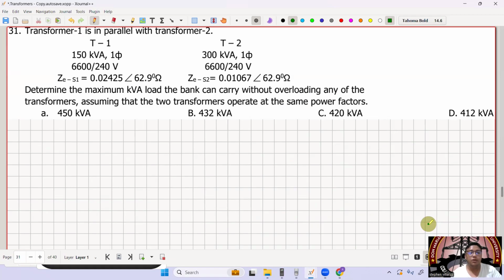Transformer 1 is in parallel with transformer number 2. T1 is 150 kVA single phase, rated 6,600/240 volts. Transformer 2 is 300 kVA single phase, same voltage ratio of 6,600/240. The Z for transformer 1 is 0.02425 at angle 62.9, and the Z equivalent for transformer 2 is 0.01067 at angle 62.9. Determine the maximum kVA load the bank can carry without overloading.